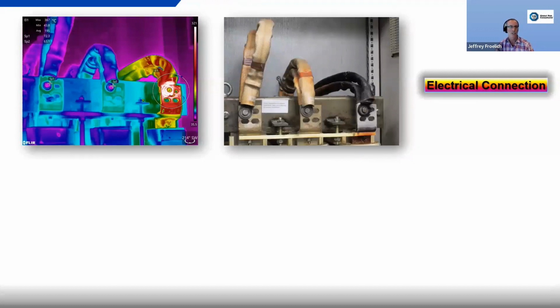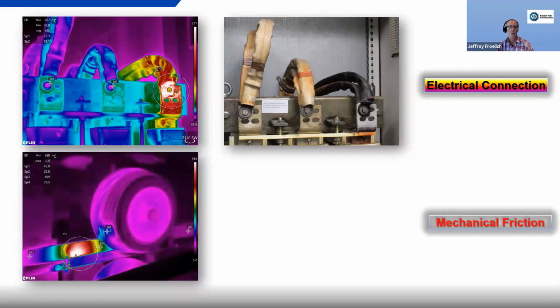Here we've got a deep well injection pump VFD reactor cabinet. And here in the connection block, we've got a C-phase lug that's over 360 degrees Celsius. Wow, it's a whopper, almost 700 degrees Fahrenheit. Of course, you can see the cable is charred and burned through, and this high resistance connection is the result of a loose, poor, deteriorated component.